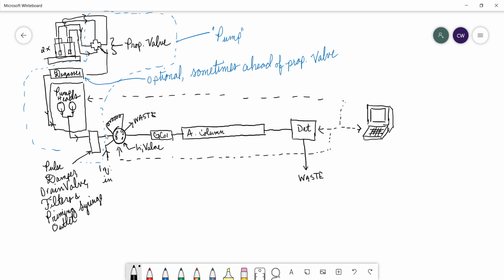Okay? From there, we flow into the injection valve, and we'll be taking a detailed look at the injection valve later, but the injection valve has one input for the pump flow, one input for an injection flow. Okay, and then there will be 2 ports that you connect with an injection loop. We'll go over that later as well. And then an outlet port that will go to waste. Okay, so whenever you do your injection, you actually inject so much sample that you overfill this injection loop, and you watch excess come out the waste line. That's how you know the injection loop is full and that there's no air bubbles in it.